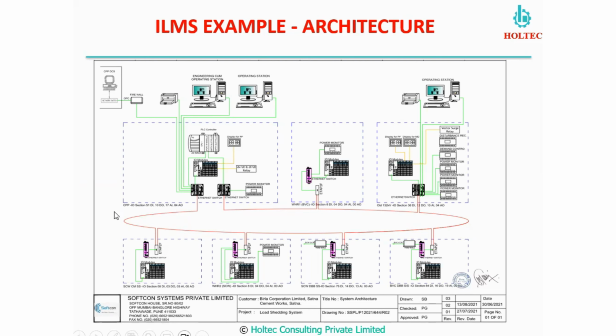So all this information will be there, and based on the logic which we develop in this controller, and with the use of SOE relays, which are very fast acting IOs, SOE IOs, we can achieve the tripping of the load or clearing of the fault in less than 100 milliseconds. Many other parameters will depend, but we can achieve this if we do all the required modifications in the existing power distribution system.